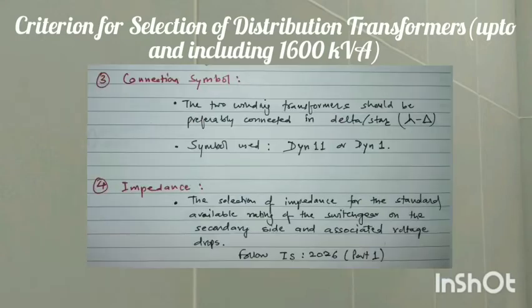Third, connection symbol. For distribution transformers, or two-winding transformers, the connection should preferably be delta-star. The symbols used are mainly Dyn11 or Dyn1.